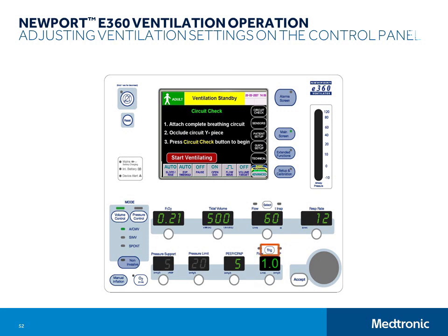Flow and inspiratory time also share a display. When you are using pressure-based mandatory breaths, the display is always set for inspiratory time. But when you are using volume control mandatory breath type, you can use the selector button located above the numeric display to determine which value will be displayed in the window and available for adjustment. Then, just like with the trigger control, you push the button below the numeric display to select it for adjustment, turn the adjustment knob to the desired value, and press Accept to implement the change.